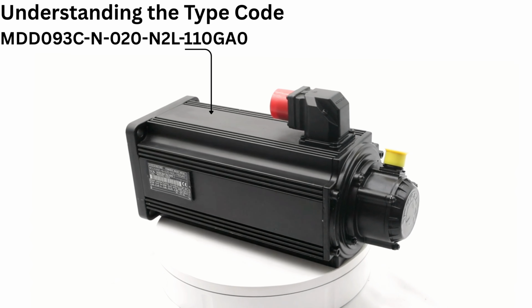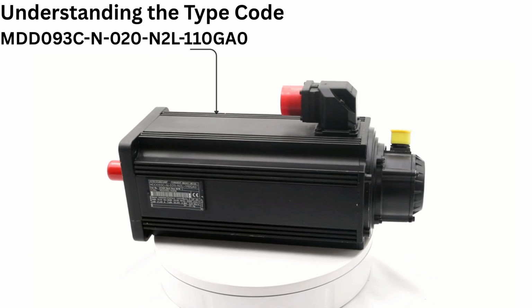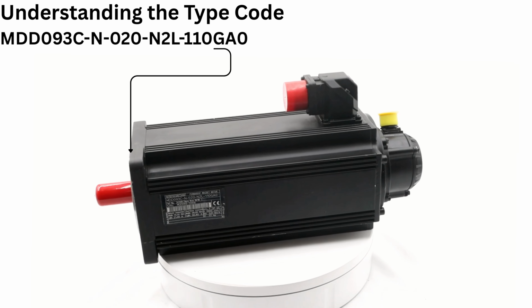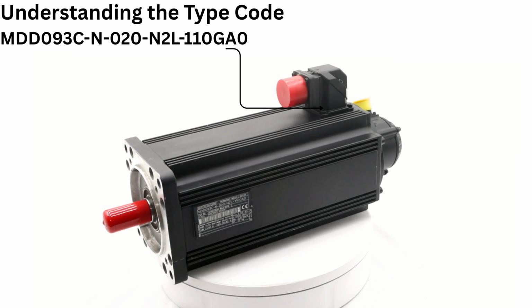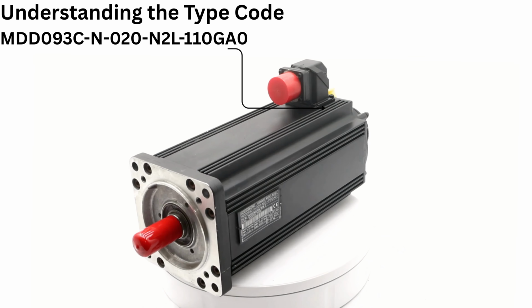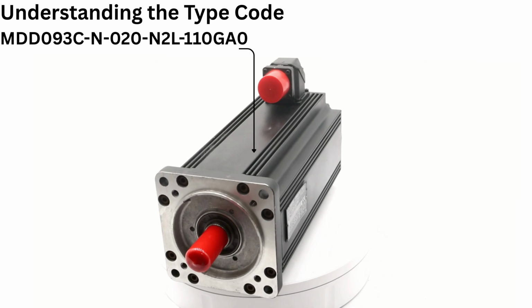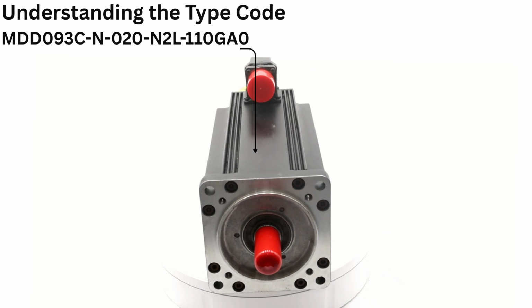110 means the centering diameter is 110 mm. G refers to the plain shaft design. A denotes that the power connector is on side A. 0 means the motor does not come equipped with a blocking brake.